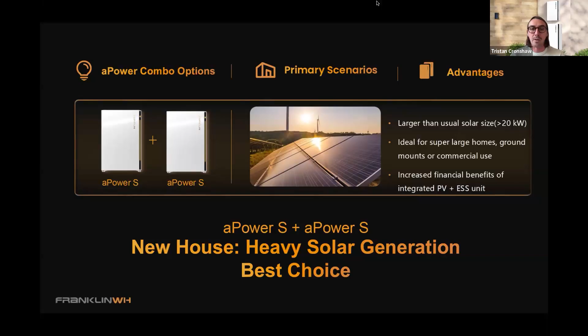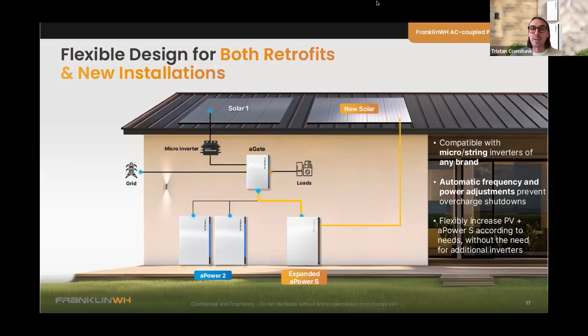aPower-S can also be scaled out in markets like Hawaii and California, which have non-exporting systems, or if you're looking to retrofit onto an existing Franklin system. It will work with an AC-coupled Franklin system or AC-coupled PV. In this example, you can see a third-party microinverter connected to the A gate, and the new PV connected directly into the aPower-S, working in tandem. So there's flexibility from a retrofit perspective as well as with new installations with the aPower-S.